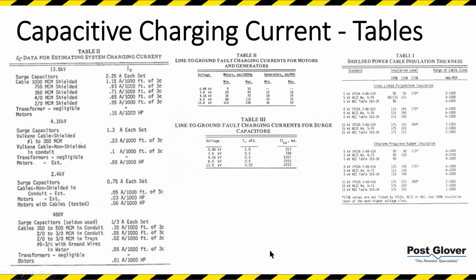So here's an example of some of the components. You just tabulate all the stuff you have in your system. Take your one line, take all X amount of feet of cable of 3/0, or 8 gauge, or whatever you have. Tabulate it all out, put it in a spreadsheet, figure out what it is per 1,000 feet, or measure your wiring first, and then use these tables for your other gear, or calculate it. It's all up to you guys, but I'm just trying to give you a window into how to start.